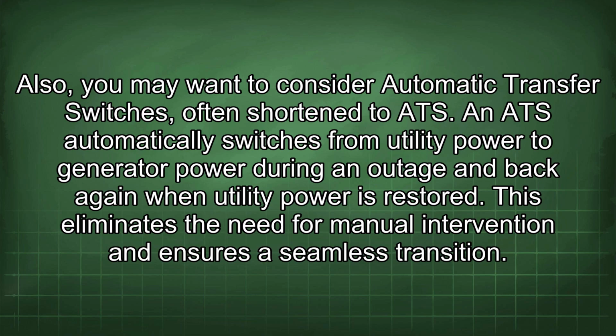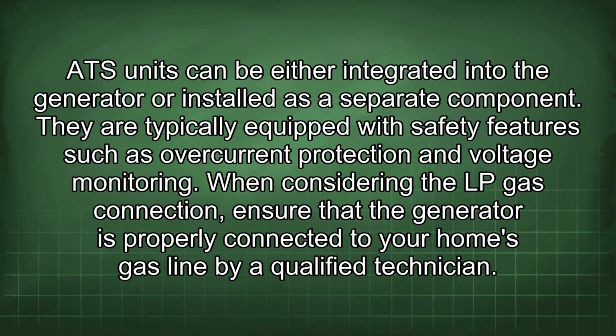Also, you may want to consider automatic transfer switches, often shortened to ATS. An ATS automatically switches from utility power to generator power during an outage and back again when utility power is restored, eliminating the need for manual intervention and ensuring a seamless transition. ATS units can be either integrated into the generator or installed as a separate component, and are typically equipped with safety features such as overcurrent protection and voltage monitoring.